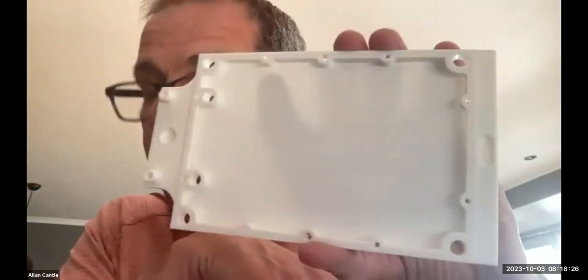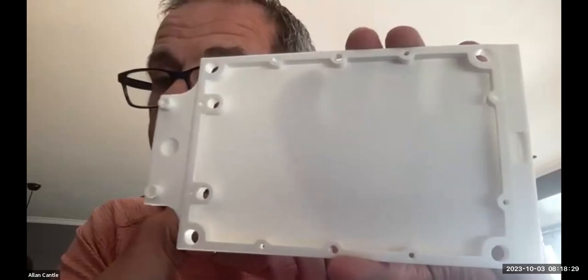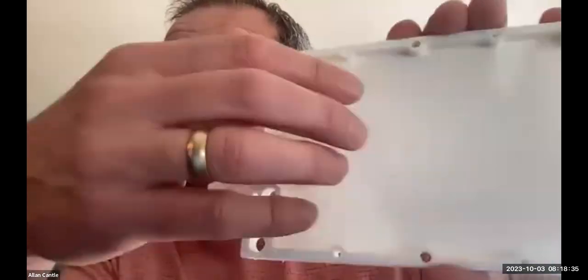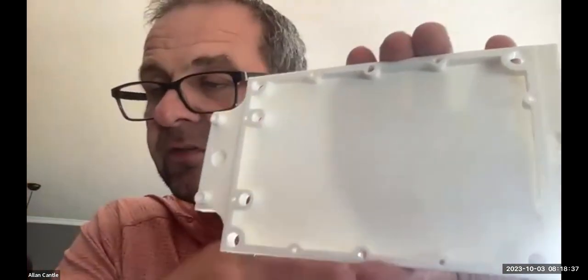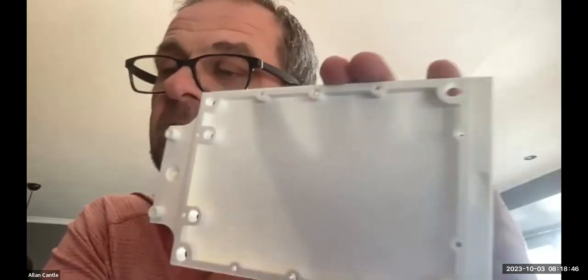So we literally immersion cool the 1 kilowatt processor, but in a very small pool of immersion liquid here. And so all of the components will be exposed to the liquid. To do that, we're working with the University of Illinois on some conformally coated copper on the components to isolate with a conformally coated insulation as well, to actually be able to use water, but we will experiment with using some inert fluids as well without any coating to begin with.